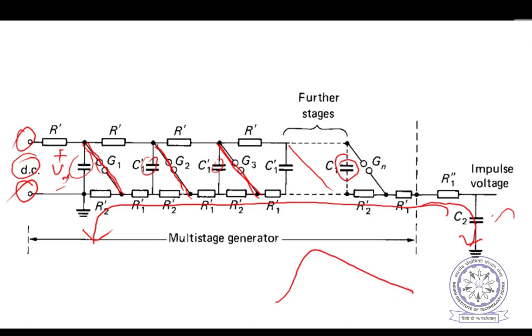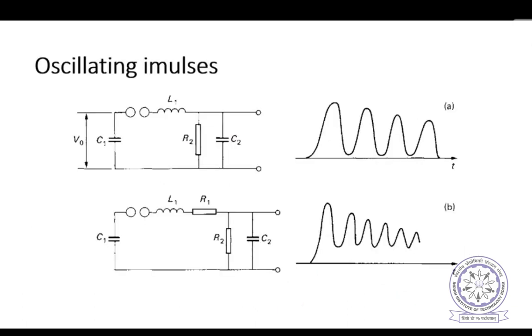These multi-stage circuits are used in every high voltage lab. 5,000, 6,000 kilovolts, or 5 or 6 megavolt generators are also available. Sometimes we may need oscillating waveforms also. In order to get oscillation, in the same circuits I have shown, simply introduce some inductance here and you will get oscillations like this. In transmission lines also such kinds of oscillations will come. To test power equipment, some customers may demand that the equipment be tested using these waveforms, so you generate these waveforms in the laboratories. These are oscillating impulses.